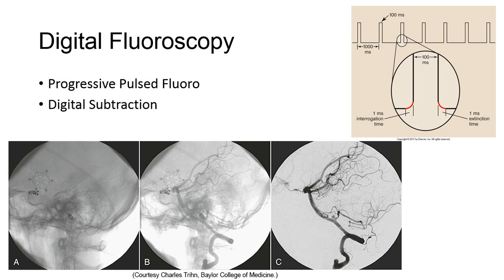Newer units have the ability of combining this mode with high MA and spectral filters made of copper or a copper-aluminum alloy to produce a higher image quality while limiting patient exposure. MA stations as high as 200 or 300 MA are possible, creating increased image quality, but also with the potential to produce some excessive patient exposure.